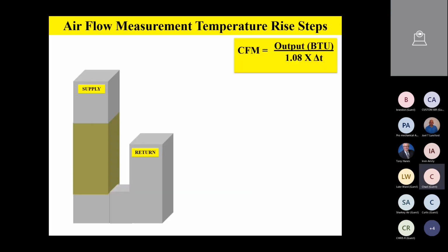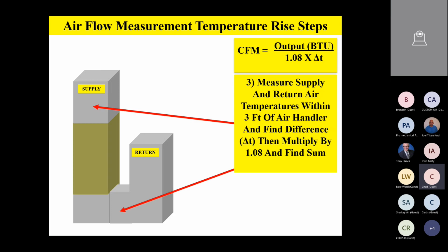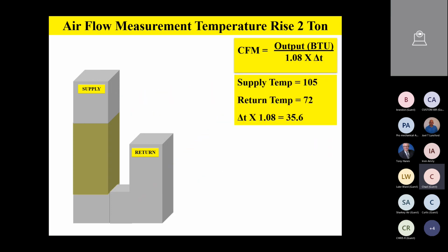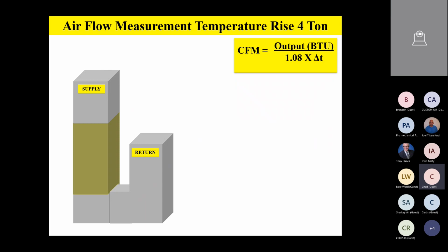Yeah, can you go back to your temperature? There you go. So let's say that I've got one of these applications that I've been speaking to this morning, with my filter inside of my air handler, and it's nearly impossible for me to get a return static pressure. Okay. Let's say that I have my manufacturer's blower performance data, and I have my formula, and I've worked out my CFM. Yes, sir. Could I take that CFM back to the blower performance data chart and then cross-reference that to determine static pressure?